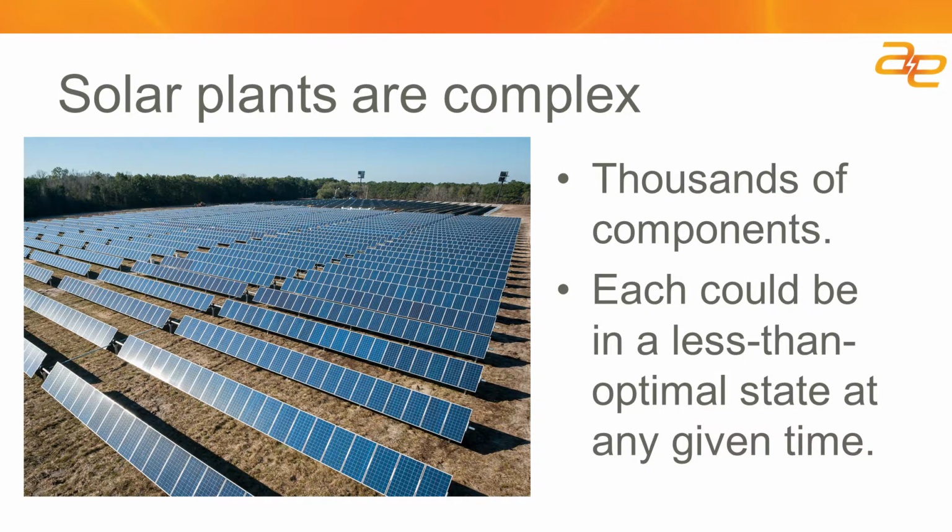Early in my career, I was given a challenge when we were building a 290 megawatt solar site. We had the first electrical block, or the electrical feeder, running, and we had about 30 megawatts online. And the energy assessment over the course of the first month of running the site was that the site was coming up about 1.5% below where the pro forma was, where energy should have been. So I got a call from the manager of the engineering department asking me to look into what the root cause of the problem might be, if this was going to be a problem that was going to scale with the site.